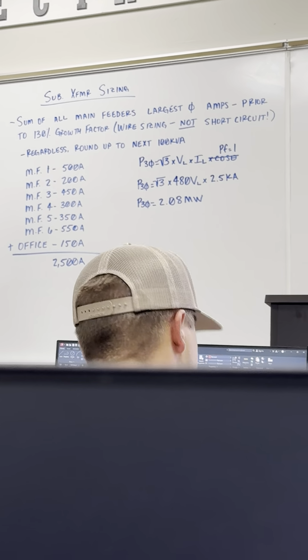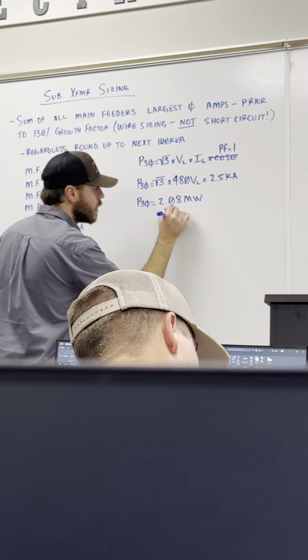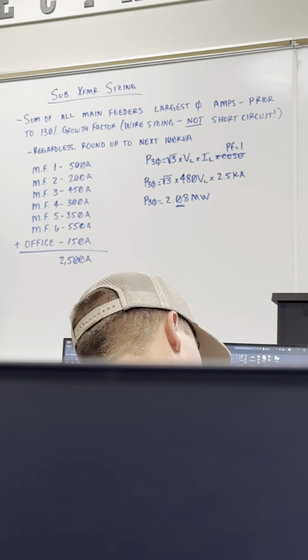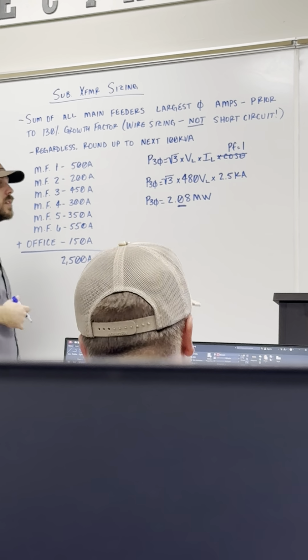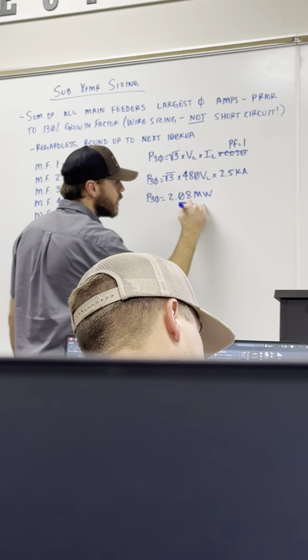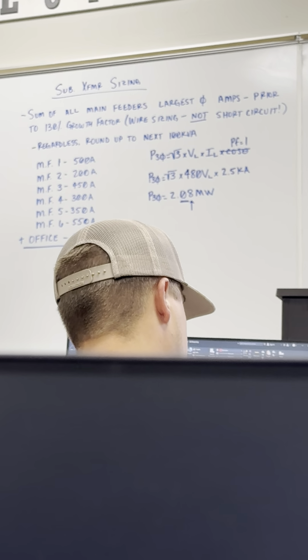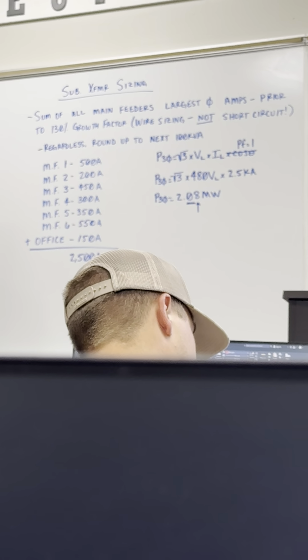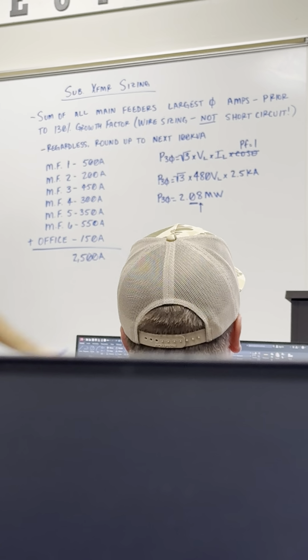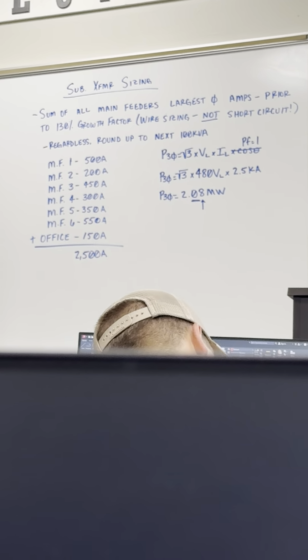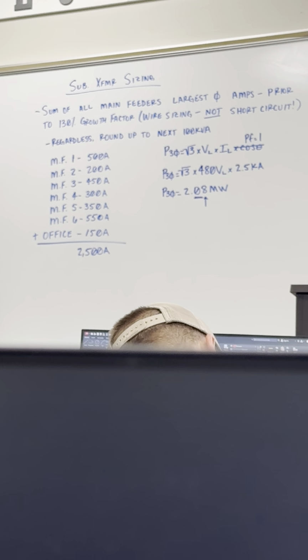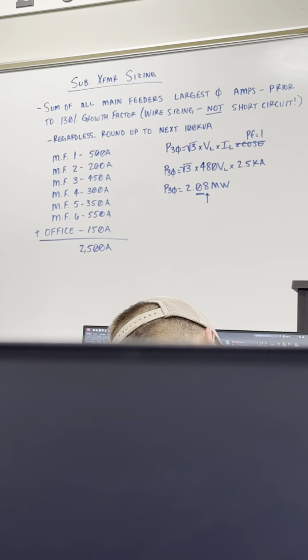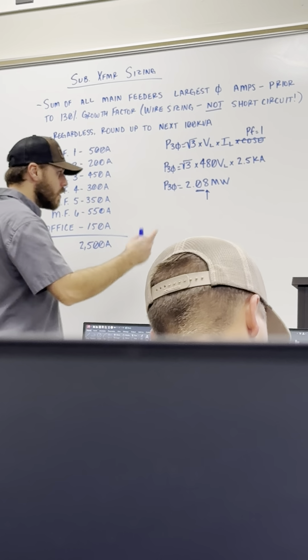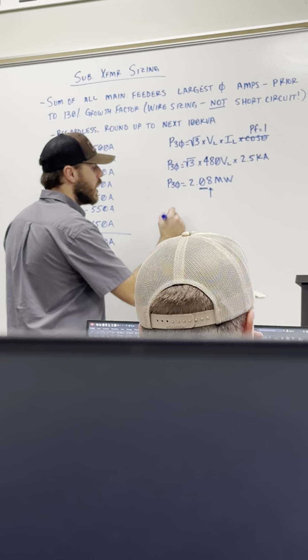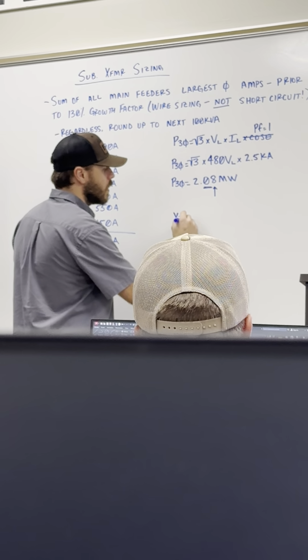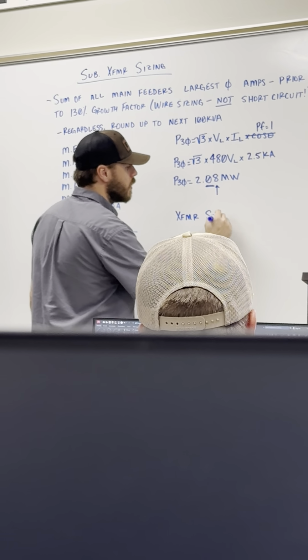So the next 100 kVA, that's the 0 right there, what I calculated. What I mean by rounding up is regardless of whatever this second decimal place is—in my case that 8—regardless of whatever that number is, we're always going to round up this first decimal place. In this case it kind of worked out because 8 is something we'd normally round up on, but even if it was like a 2 or a 3, we're still going to round up. So in this case, what would that round up to? 2.1, there you go.